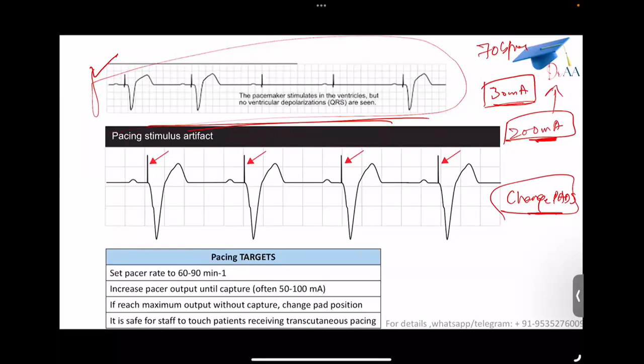Pulse is what we call the mechanical capture. Pulse should be 70 beats per minute because you have selected 70 here. If it is 70, then mechanical capture is also there. For example, you increased till 100 milliamps, you have got an electrical capture. You check the pulse, it is only 40. You have selected 70, but it is 40. Then again, you increase the energy till you get a mechanical capture, that means till you get a pulse of 70 beats per minute. That finishes transcutaneous pacing.